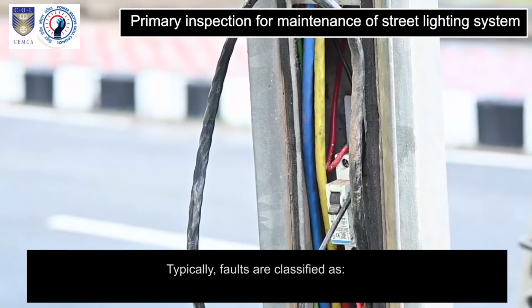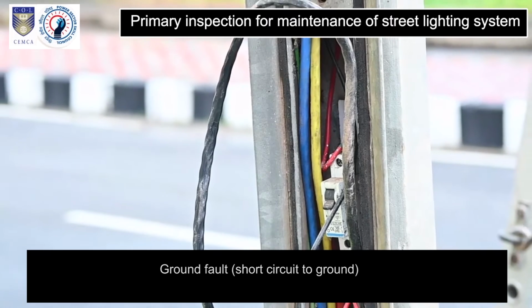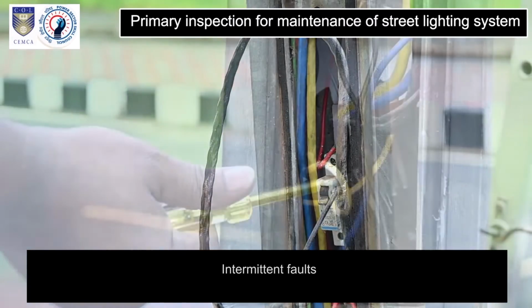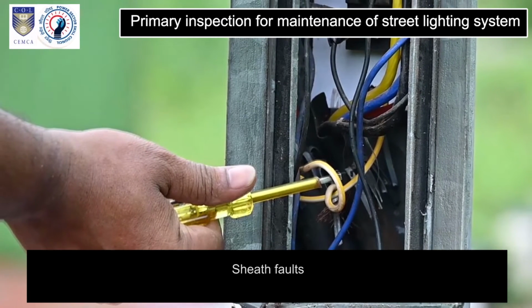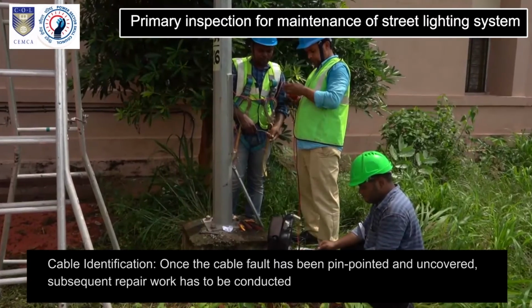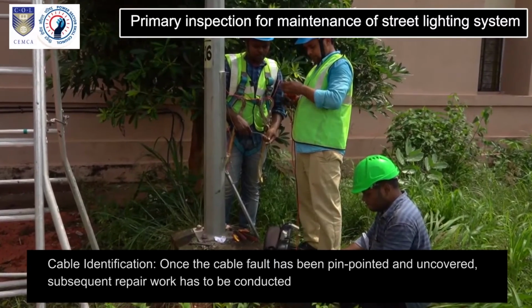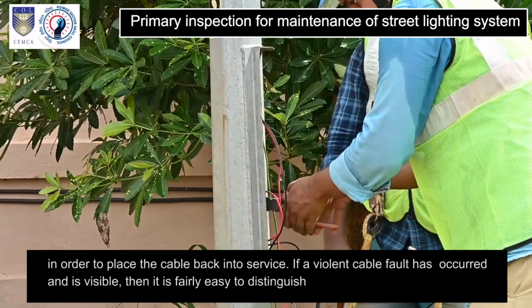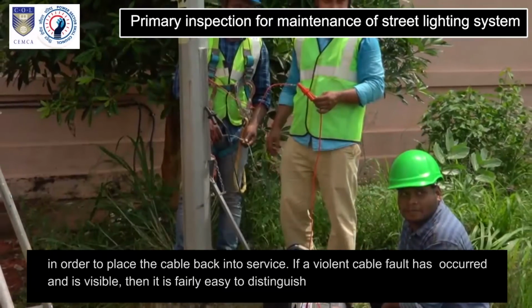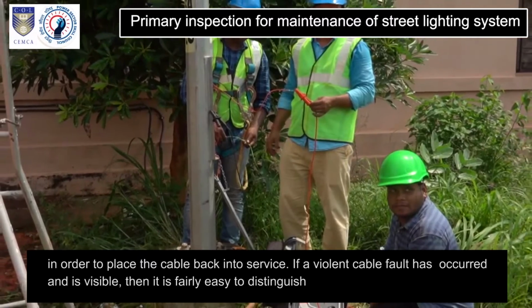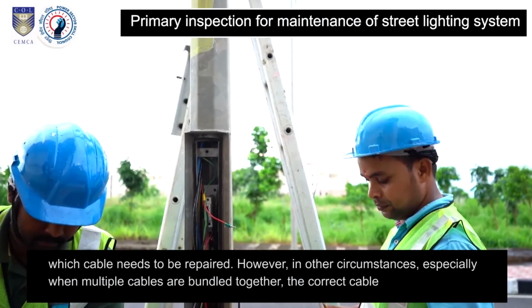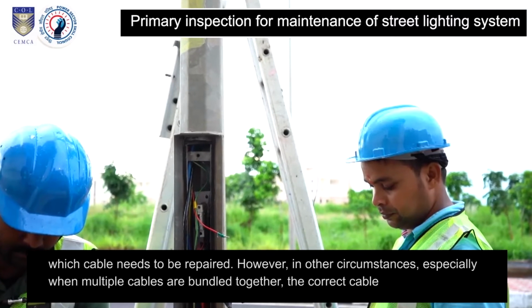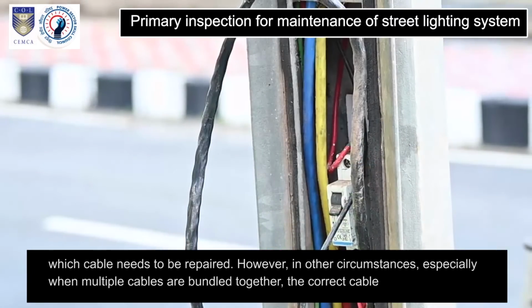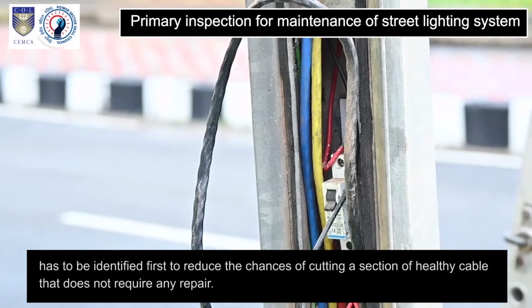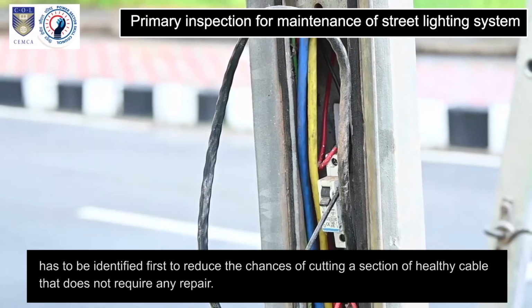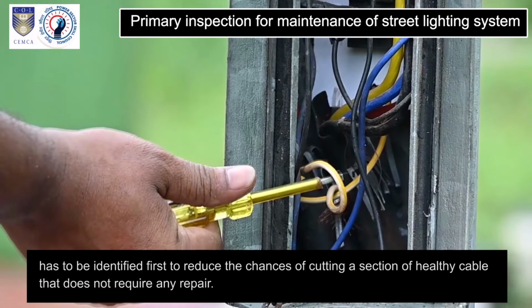Typically, faults are classified as low impedance, short circuit, ground fault, short circuit to ground, cable breaks, intermittent faults, sheath faults. Cable identification. Once a cable fault has been pinpointed and uncovered, subsequent repair work has to be conducted in order to place the cable back into service. If a violent cable fault has occurred and is visible, then it is fairly easy to distinguish which cable needs to be repaired. However, in other circumstances, especially when multiple cables are bundled together, the correct cable has to be identified first to reduce the chances of cutting a section of healthy cable that does not require any repair.